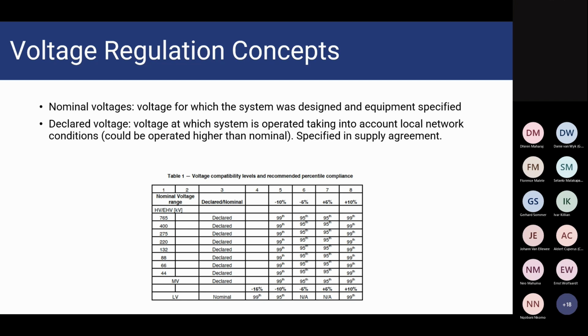On LV, your 95th percentile is compared with -10% and +10%. So the lower limit is compared to minus 10% and not 6% as for MV and up. That's the main difference. So if you set it up on your system, just make sure you set the declared voltage up correctly, and the nominal on LV.